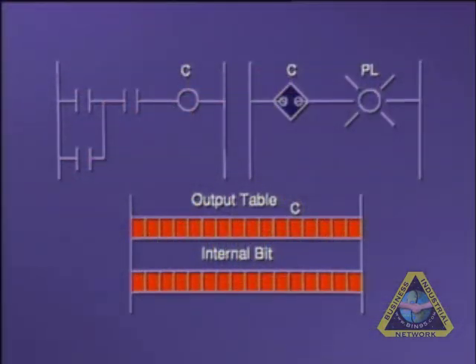If the output address you programmed corresponds to an output bit in the output table, the processor will turn on the output and therefore the field device connected to the module's terminal whose location maps the output coil address.